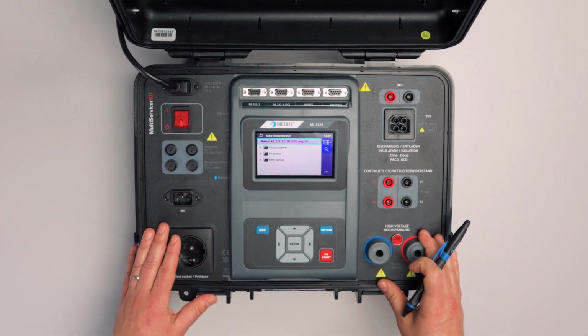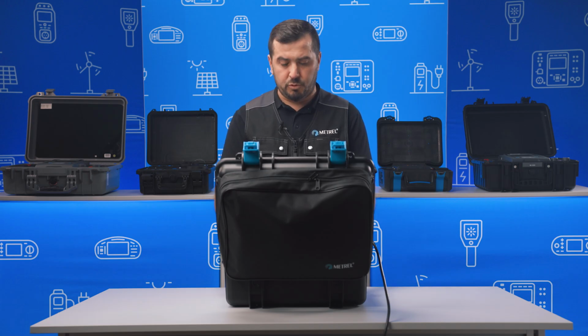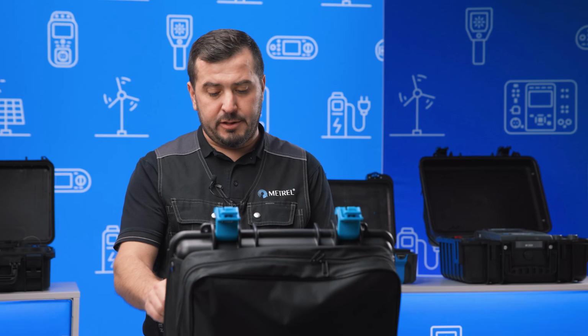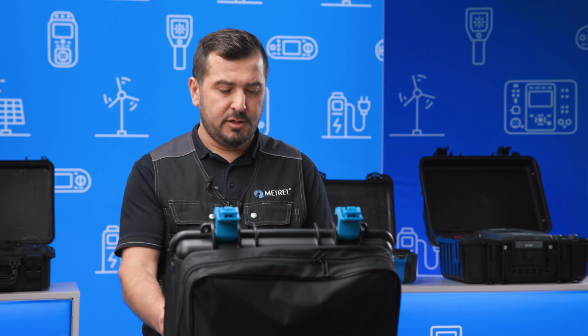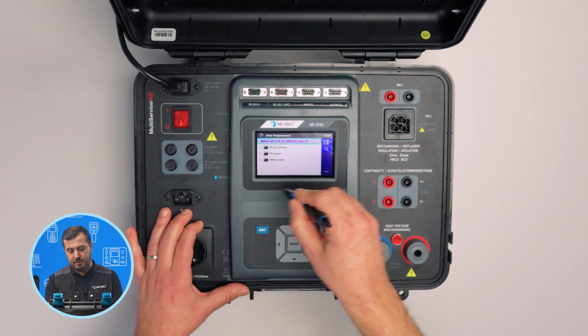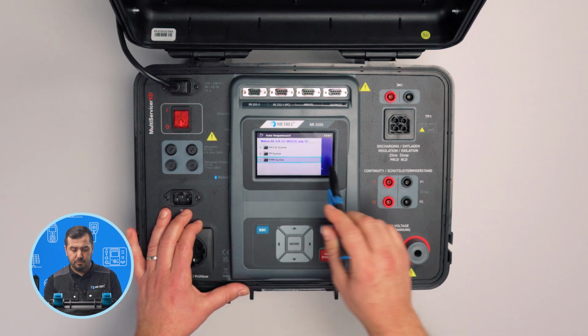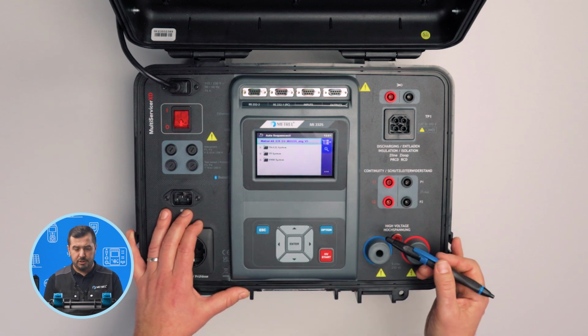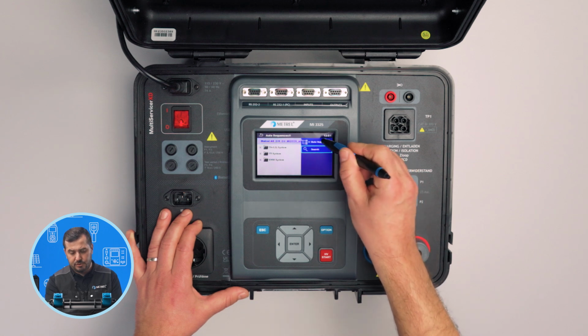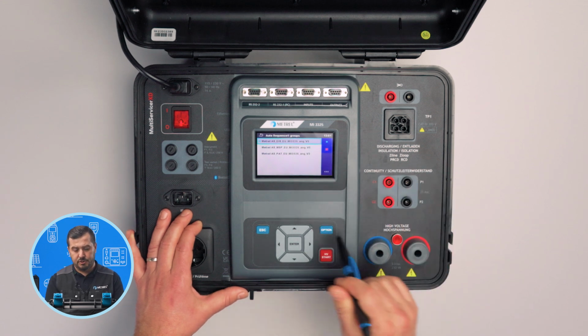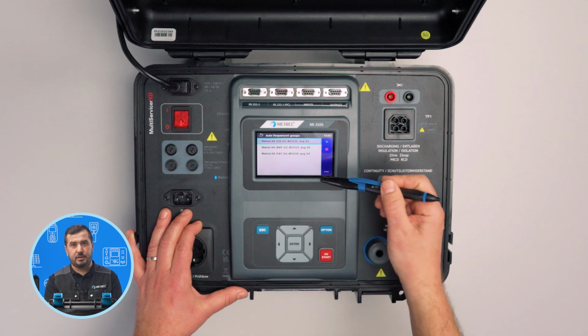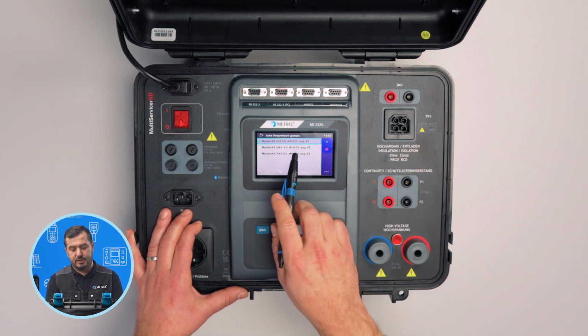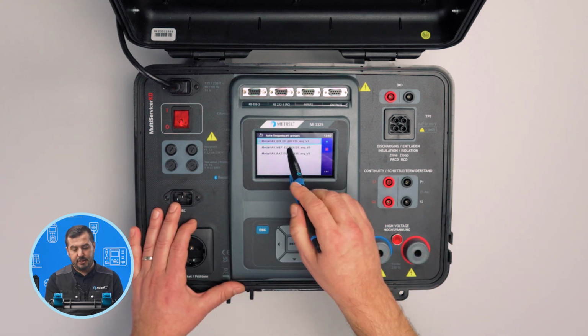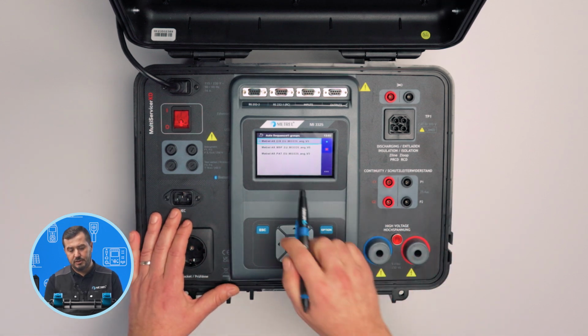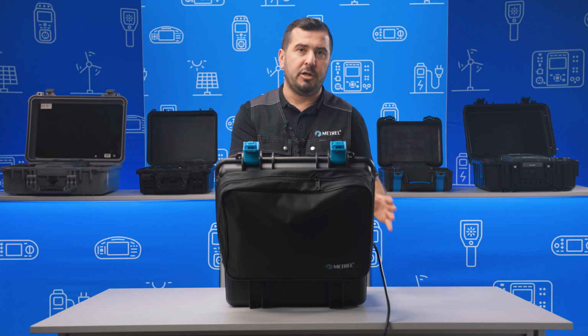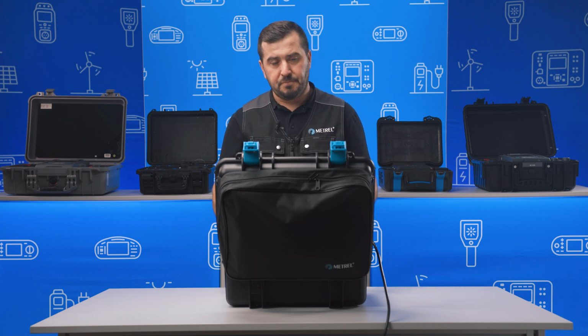Each instrument delivered comes supplied with at least 3 different groups of auto sequences. As I was explaining before, in the general settings there is a special menu where you can choose between these groups. There is also a shortcut in this auto sequence menu. So for example, please pay attention. If I click here on the header of the auto sequence menu and choose the auto sequence groups, it will redirect me back to the general settings menu, where I can see what auto sequence groups are available. So the first one is dedicated for safety of electrical installation, the second one for testing machines or switchboards, and the last one for testing on, let's say, portable equipment or generally electrical equipment with plugs.